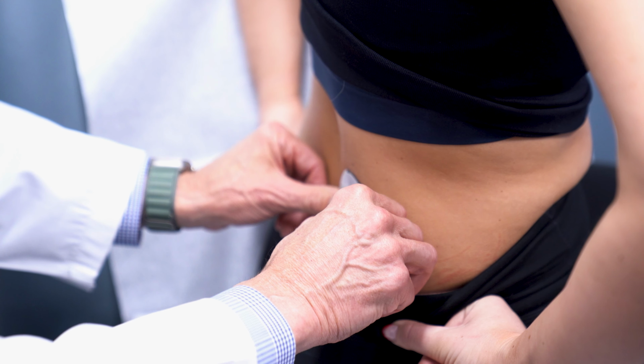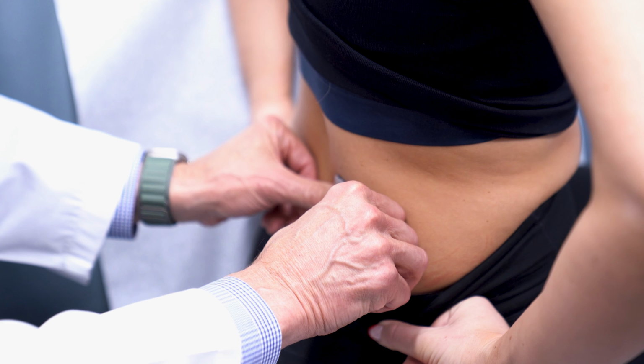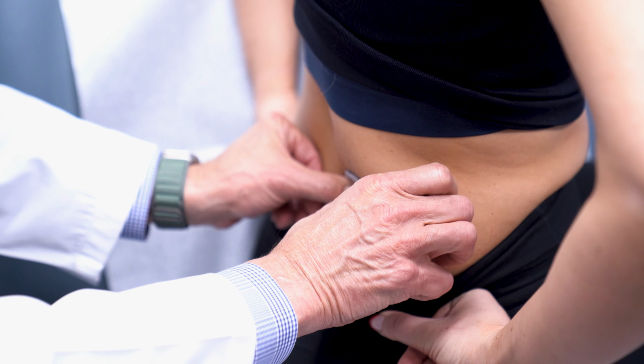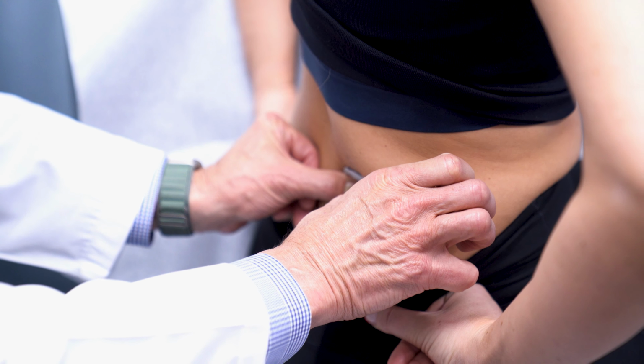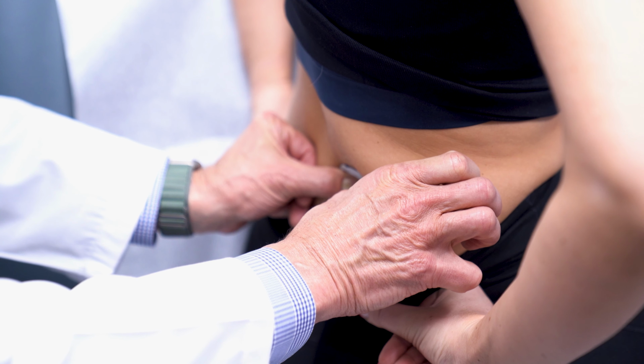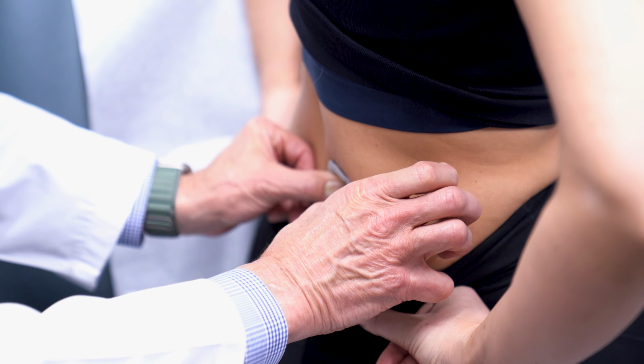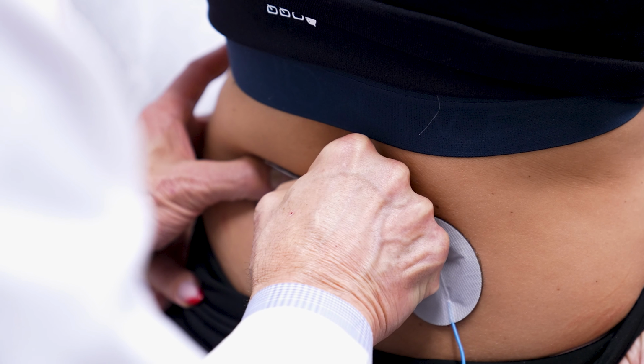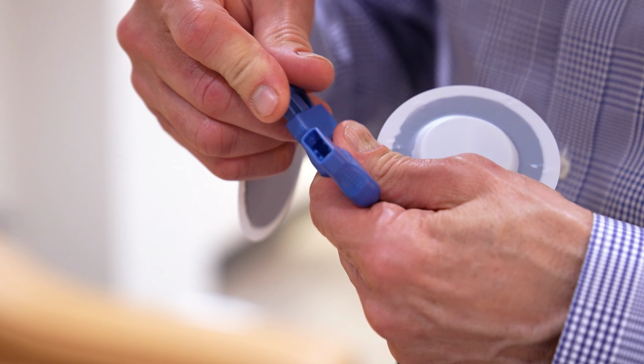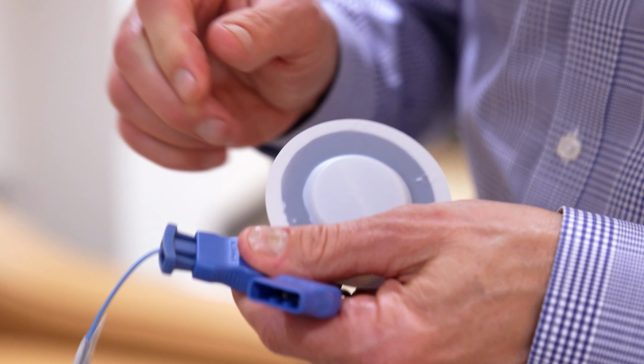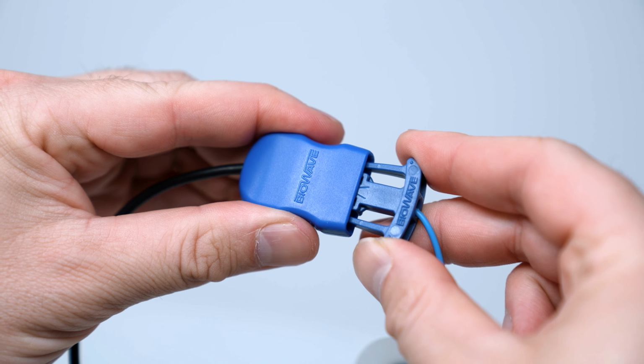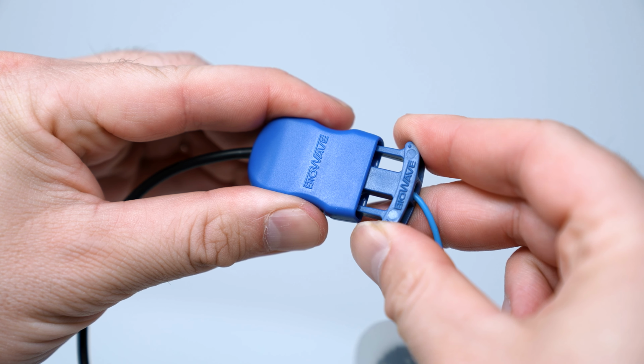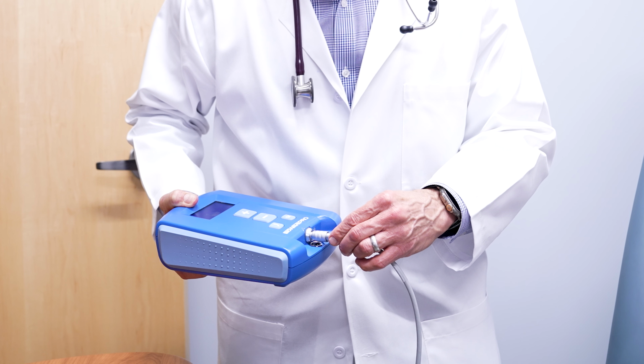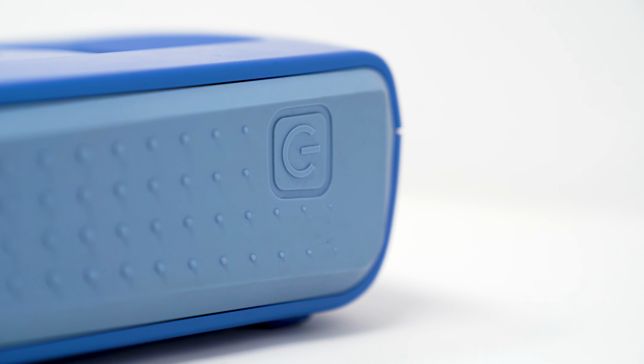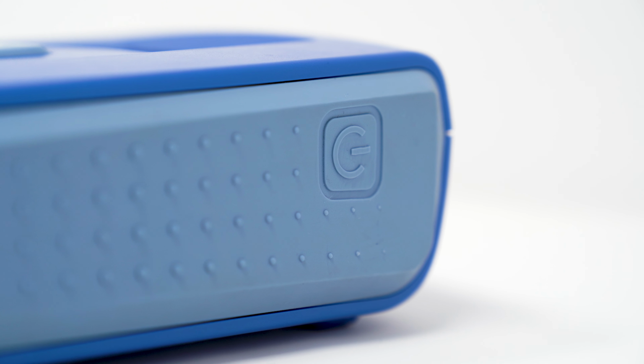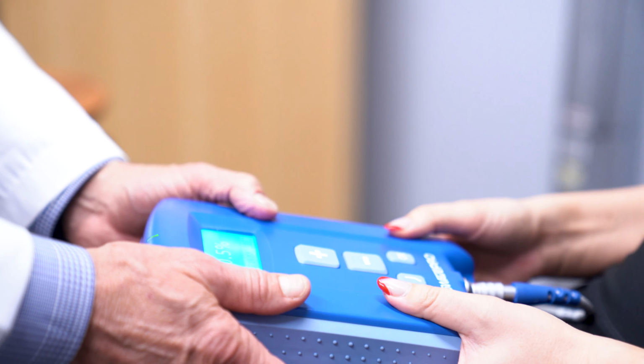Using firm pressure, approximately 10 pounds of force, perpendicular to the back of the electrode, press the center of the first electrode to insert the microneedle array through the epidermis. Repeat this process for the second electrode. Plug the blue connectors from the end of the lead wire cable into each of the blue connectors at the end of each of the electrodes. Plug the single end of the cable into the BioWave Pro stimulator. The provider presses the power button to turn the device on and hands the Pro unit to the patient.